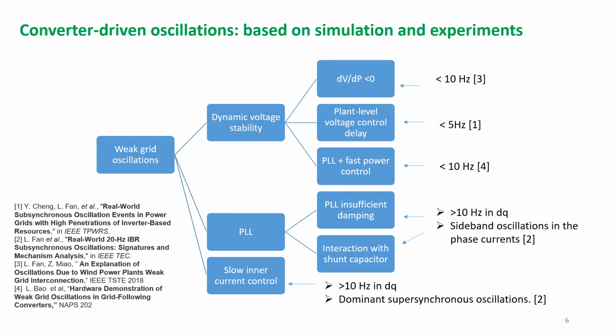Also in the fundamentals, we can build any kind of model if we know what is inside, play with the parameters, and create lots of different oscillations. For example, in this chart, I have provided various causes of weak grid oscillations. They can roughly be said to have three different types. This is all based on simulation, like a dynamic voltage stability issue, a PLL related issue, or a slow inner current control issue. All of these can again be classified into various issues. For example, even within the dynamic voltage issue, you can see it is because of the outer loop or the plant level that they are different.